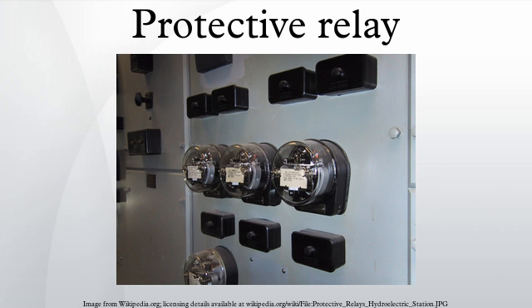Directional relay. A directional relay uses an additional polarizing source of voltage or current to determine the direction of a fault. The fault can be located upstream or downstream of the relay's location, allowing appropriate protective devices to be operated inside or outside of the zone of protection. Synchronism check. A synchronism checking relay provides a contact closure when the frequency and phase of two sources are similar to within some tolerance margin. A sync check relay is often applied where two power systems are interconnected, such as at a switch yard connecting two power grids, or at a generator circuit breaker to ensure the generator is synchronized to the system before connecting it.